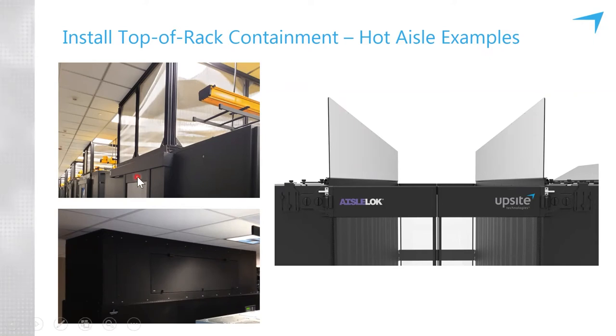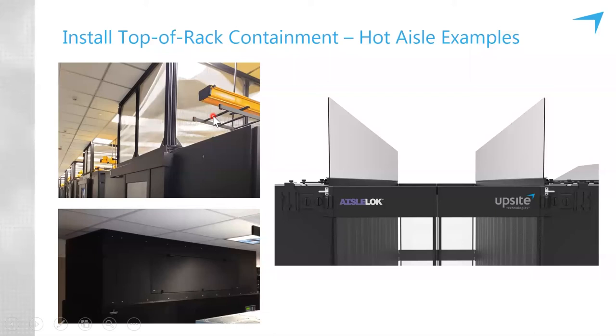There's also a role for flexible hot aisle containment using curtains — flexible polycarbonate wall material, similar to what you'd see in meat lockers. This is especially useful when you have varying elevations of power and cable management. You can see a ladder rack and a yellow fiber tray running parallel to the rows, but often things cut across the rows at different widths, heights, and elevations. It's easier to trim curtain material to navigate around those overhead obstructions and still maintain a good seal.